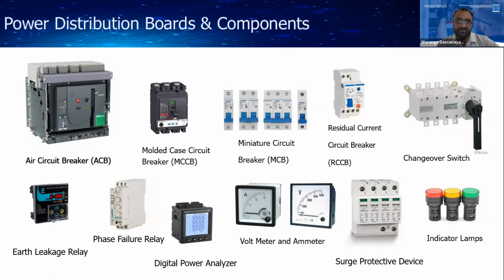Then the next one is the phase failure relay, which we call PFR. It detects a phase failure in the system, because in a three-phase system, all phases have to be healthy to operate a three-phase load. If one phase fails, the equipment may be damaged. Therefore, to avoid that damage, we use phase failure relays to detect a phase failure or an under voltage in the system and trip the main circuit breaker.